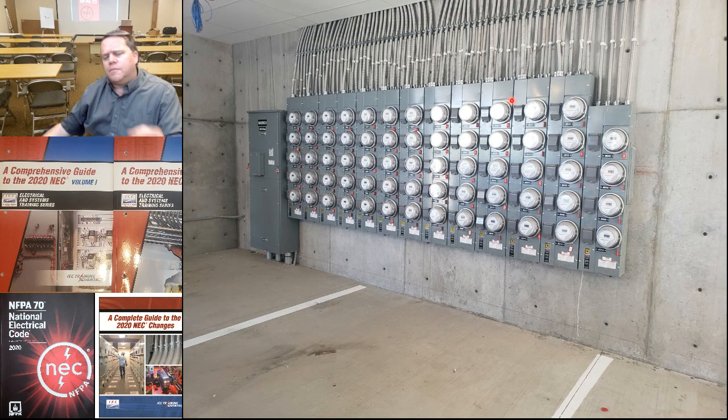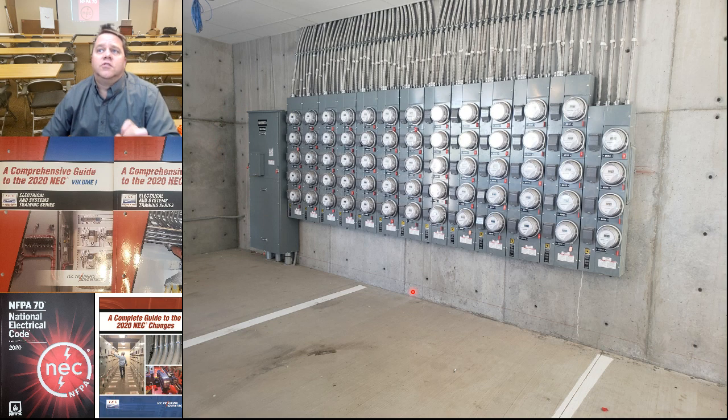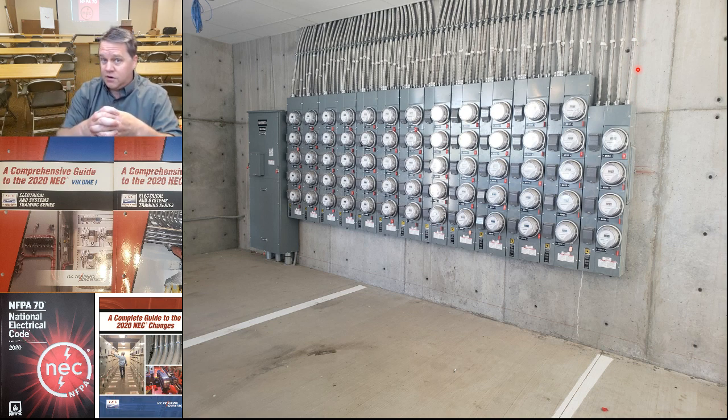Where you would find this is for apartments, large multifamily facilities, where you have a 120/208 volt, 3-phase service, and you're just supplying 2 hots and a neutral to the individual apartment units, so single phase 208. So here you can see all of these MC cables. They've got black, red, white, and then black, blue, white, and then red, blue, white, just to keep things balanced. And in those cables, we'll be counting all 3 of those conductors as current carrying. Now, in and of itself, that's not a problem. These cables have 3 current carrying conductors, so no big deal. If I were to bundle them together, however, then I would have 6 or 9 or 12 or however many I bundle.